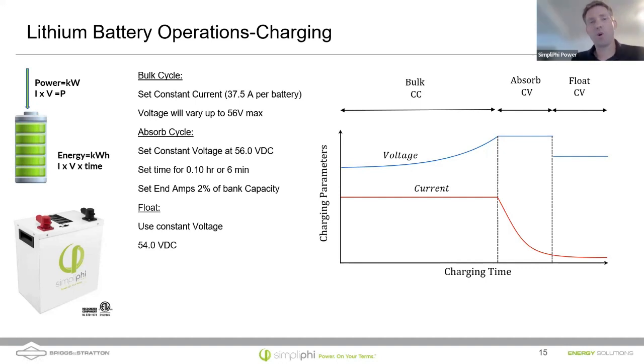Some batteries will call it the bulk voltage or even the bulk termination voltage. There's another voltage not to be confused with this, called the rebulk voltage - that's the low voltage your battery will reach when a charging cycle will restart. As your battery is discharging, eventually that voltage will come down, and once it hits the rebulk voltage - maybe you set it at 51, 52, or 50 volts - that's when the charging cycle will initiate. So when I'm referring to a bulk cycle or bulk termination voltage, I'm talking about the 56 volts we go to for the absorb, which is constant voltage on absorb.